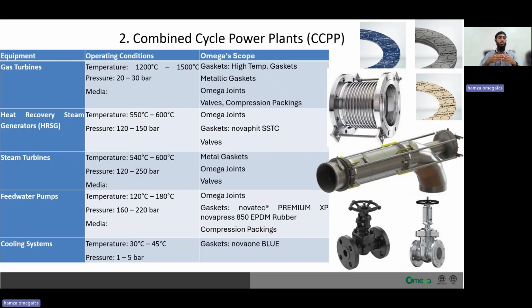Now let's talk about the heat recovery steam generators. Heat recovery steam generators usually see temperatures of 550 degrees Celsius to 600 degrees Celsius and pressures from 120 bar to 150 bars. Here again, graphite gaskets play an important role in sealing the steam and the fluid within the system. Omega joints play an important role here, as we'll see in the next few slides. Steam turbines: again, we see temperatures of 540 to 600 degrees Celsius and pressures of 120 to 250 bars. Similar to the gas turbines, here we use metallic gaskets as well as omega joints for the expansion joints, and valves.